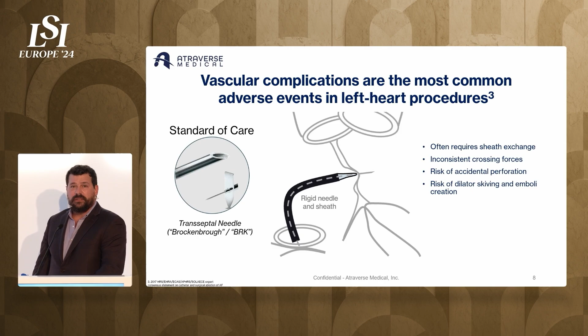And so Atraverse is pioneering the hot wire system. We have a radio frequency or RF guide wire. You have the same workflow where you position adjacent to the septum, but instead of mechanically advancing your way across the septum, you just press the button, use a little blast of radio frequency energy and/or electrocautery, if you will, denature the tissue and gently advance across. And then you can introduce your therapy device over the wire and proceed to deliver your therapy. Pull out your RF guide wire and complete the procedure.